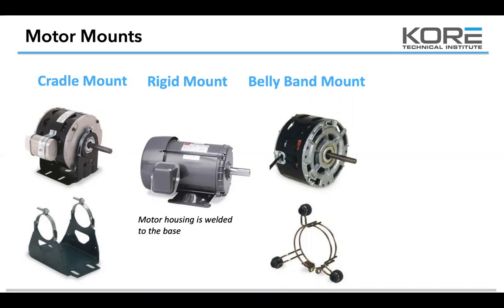I can't tell you how many times a year, in the summertime, that one gets guys. It's probably the most common callback I get on AC calls: the bearings have gone out in the motor. It runs fine when they start it up, after they reset the high limit and wash the coils. Everything's fine. It seems good. They see the motor's running fine. They drive away, and then they're back. Them or somebody else is back there within a few hours or the next day with the same situation. So run the motor, touch the motor. If you guys want to know the difference between a warm motor and a hot motor, start touching the sides of your motors when they're running, just to see what the difference is. Log that in your brain.